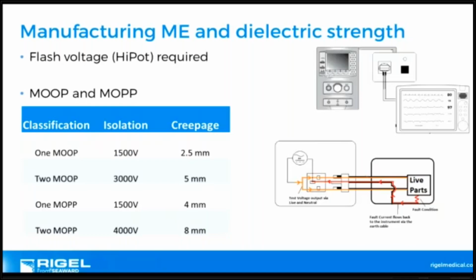Well, anyway, in Rigel Medical, we've had a lot of manufacturers getting in touch, and we just need to demystify or at least give people some kind of guidance. Remember, this whole presentation, it's not a directive. Rigel isn't telling you what to do. You can't come back and say, Michael, you told me you should be doing this. No, this is best practice. This is guidance, but still, we're just giving you what the standards say and the best practice behind electrical safety testing. Not a directive. Must be clear on that.